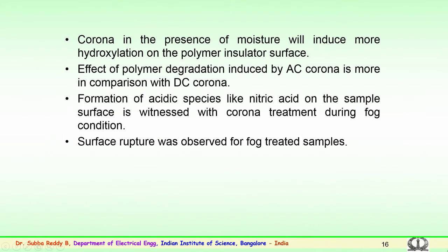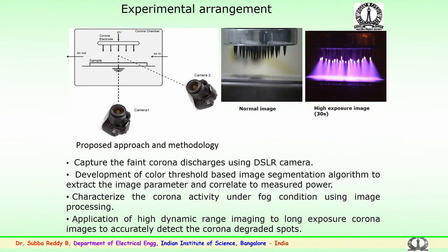So, once this phenomenon occurs, the hydrophobic properties of the material could be weakened, and the sample is likely to degrade faster in the field. Further, the measurement of corona performance in the field is normally done by looking at the corona discharges using UV cameras or corona cameras, where you could see the corona discharges which are impinging on the sample.